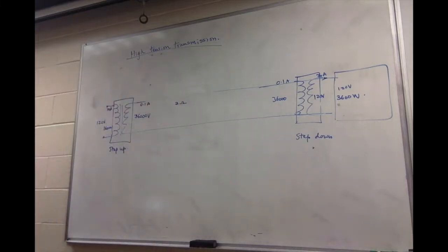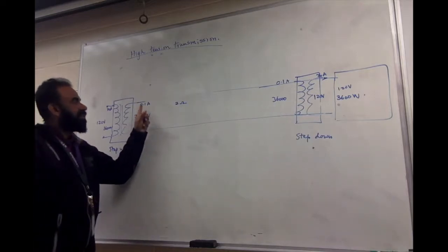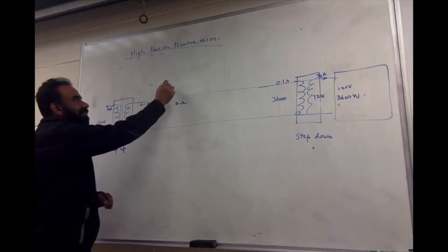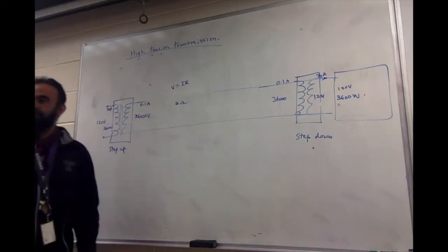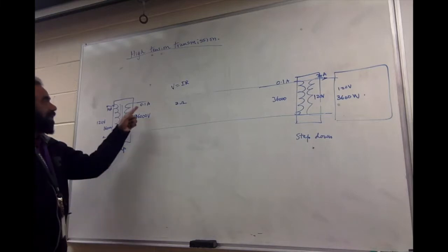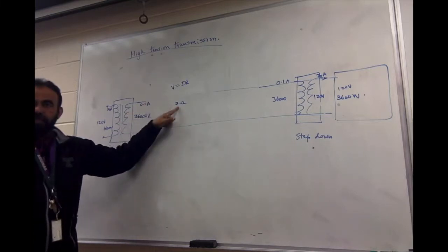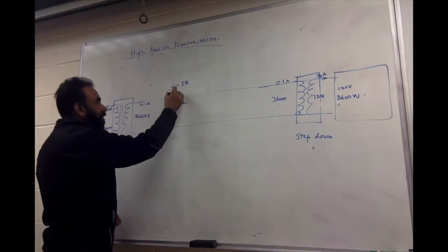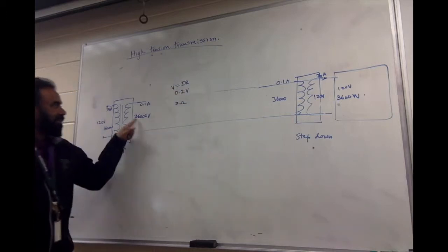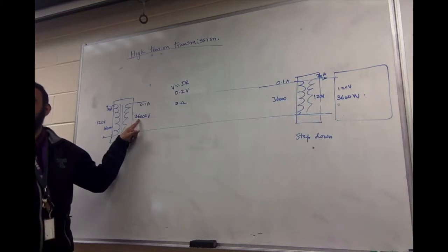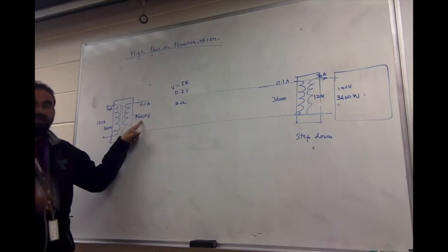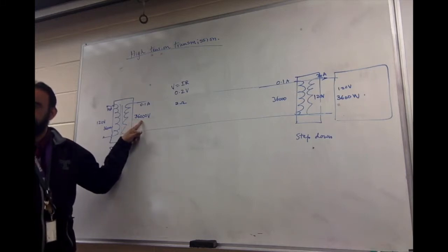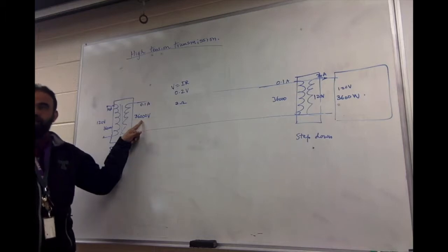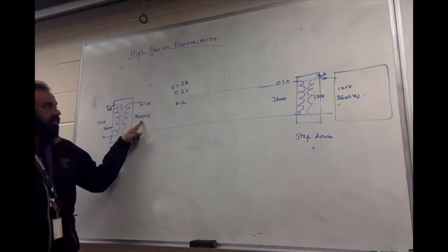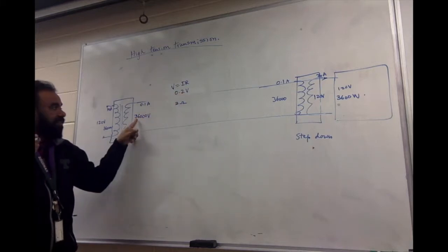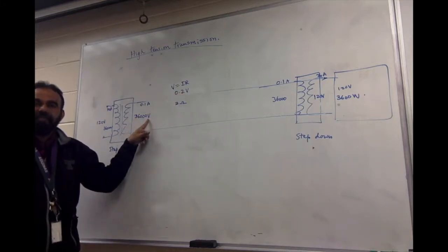Now let's look at losses. How many volts are lost through the wires? The current is 0.1 amperes flowing through 2 ohms, that's 0.2, so the voltage loss is 0.2 volts out of what? 36,000. You're losing 0.2 volts out of 36,000. There's nothing, it's not like 60 volts lost out of 120, right? This is only 0.2 volts lost out of 36,000, so it's nothing at all, that is not a big loss.